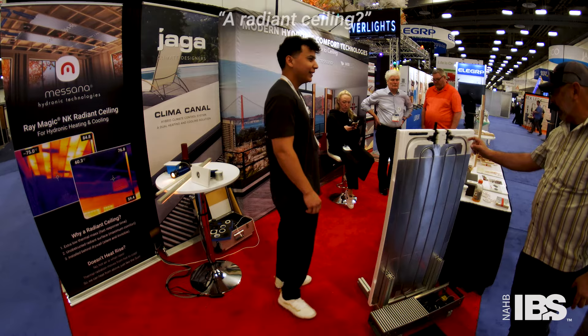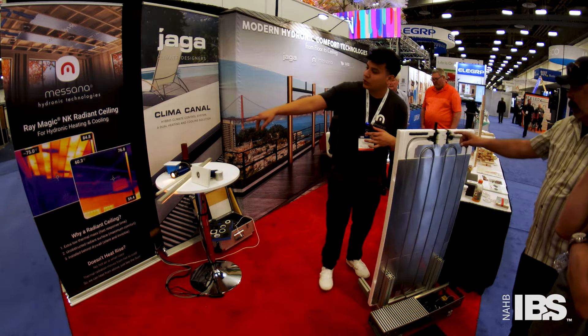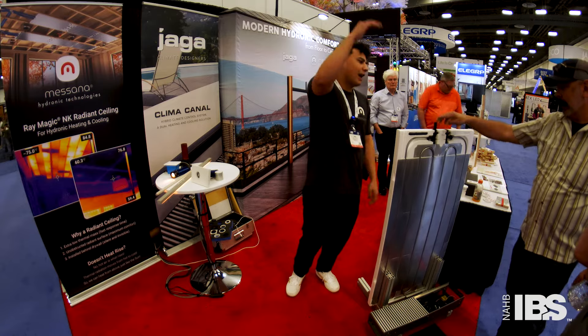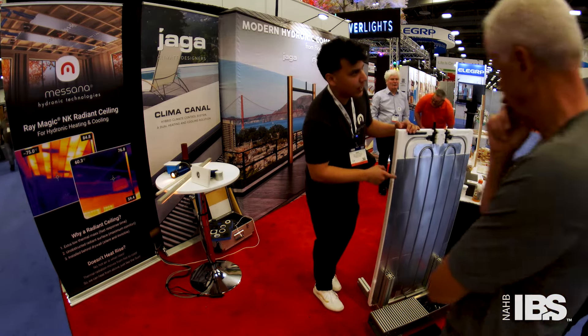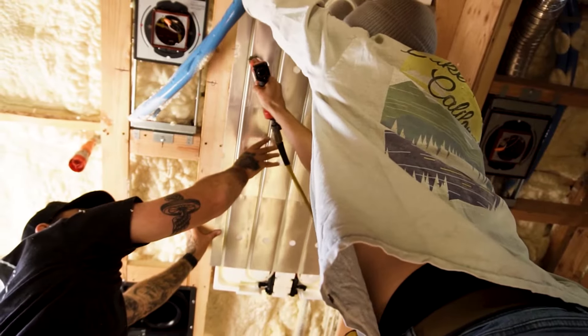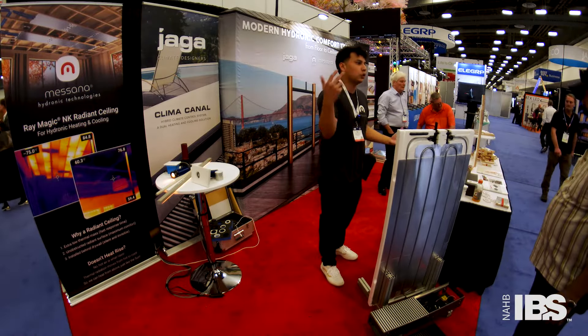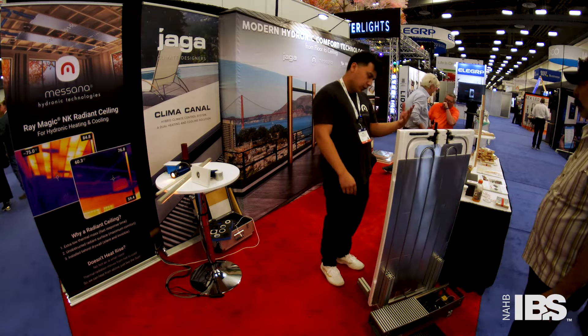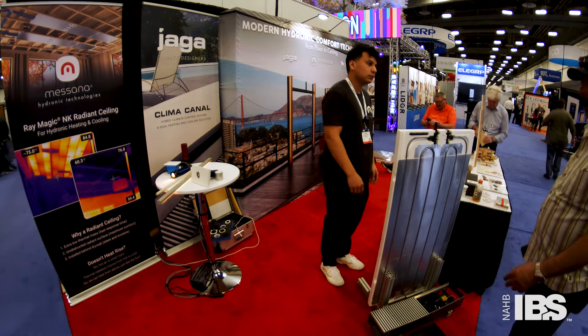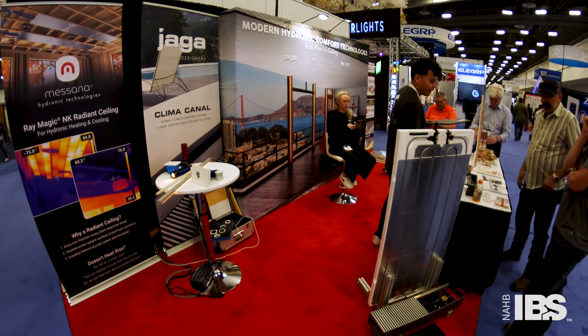You guys have a radiant ceiling? Yeah — we moved it to the ceiling because our goal was to provide radiant cooling and we needed a fast-responding, low-mass system. You can see thermal images here of it in cooling and in heating. That's great because you're combining your energy source — you just use an air-to-water heat pump. You buy the panels typically in 2x8. You break off this EPS edge and staple or screw up the wing. It's about 8 pounds dry and 10 pounds wet for the 2x8 — about 2 pounds of water. For cooling you can use a chiller, but typically an air-to-water heat pump generates hot and cold water. Our controls talk to your heat pump, circulator pump, and even domestic hot water — it's a very comprehensive control platform we developed for radiant cooling.